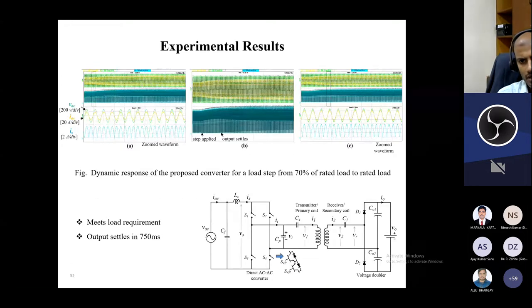We performed a step response test. We have two loops, and the first waveforms showed the performance of the inner loop, where we were able to get the sinusoidal grid current. To check the outer loop, we provide a step command in the load—here it is a current control in the load, so we are changing the load current. In the middle diagram, a step is applied at one point, going from 70% of the load suddenly to 100% of the load demand. It took about 750 milliseconds, which is our designed value for the outer loop, and within that time it reached full load.